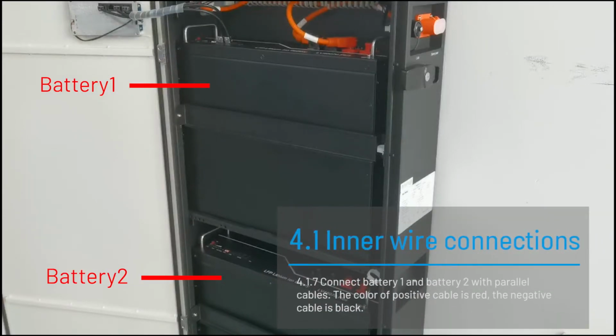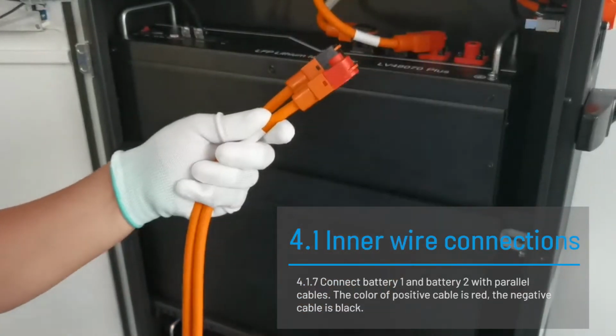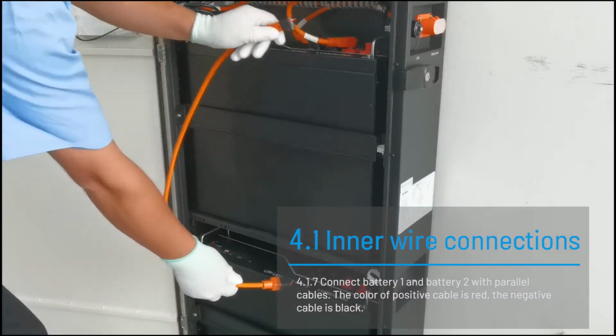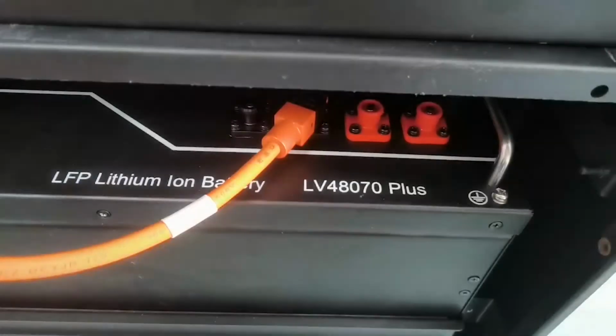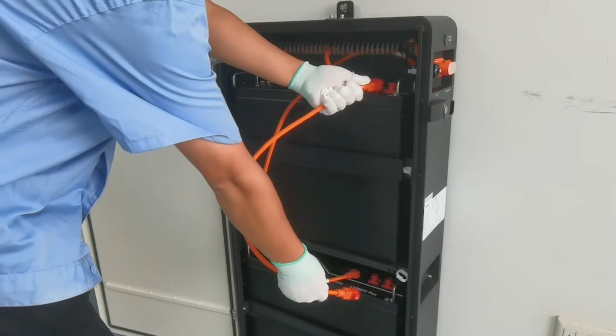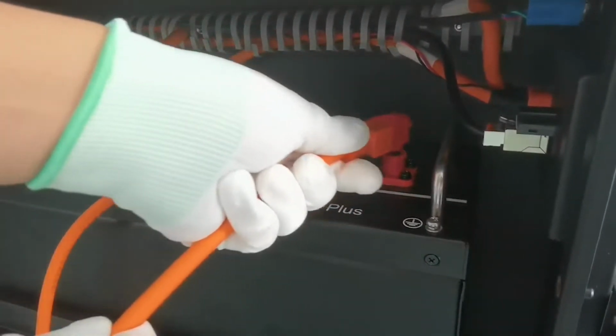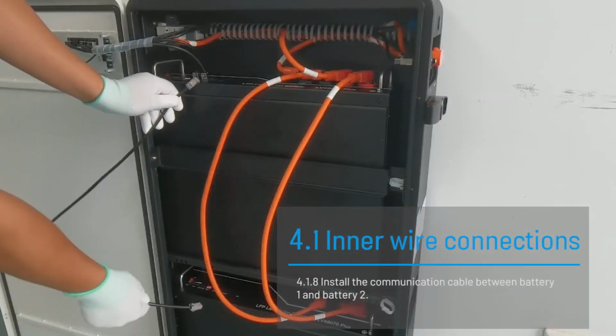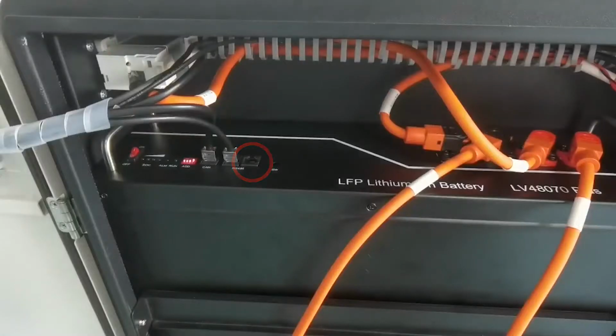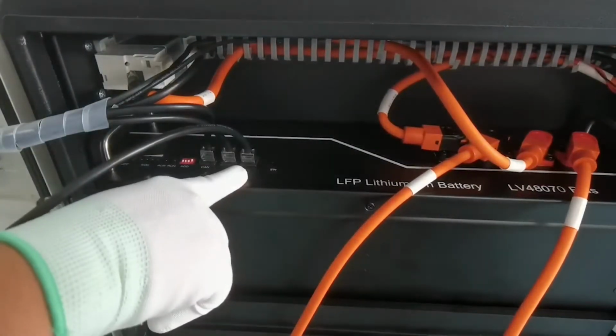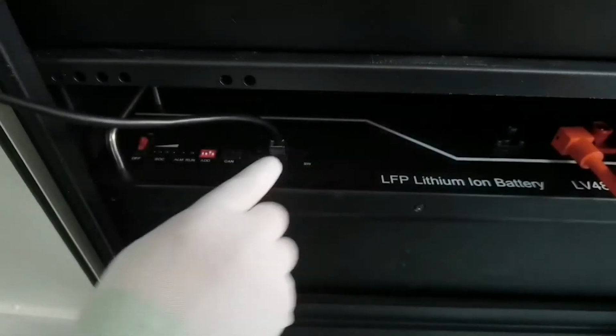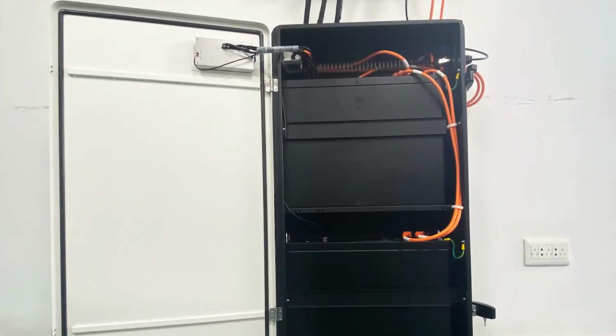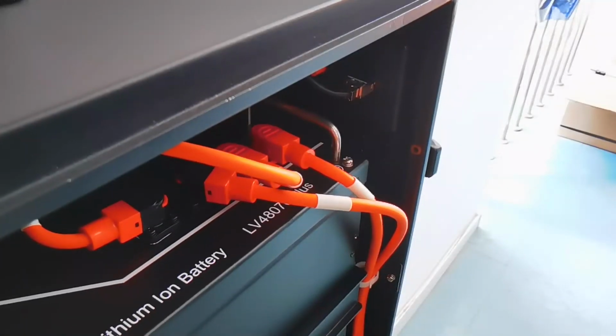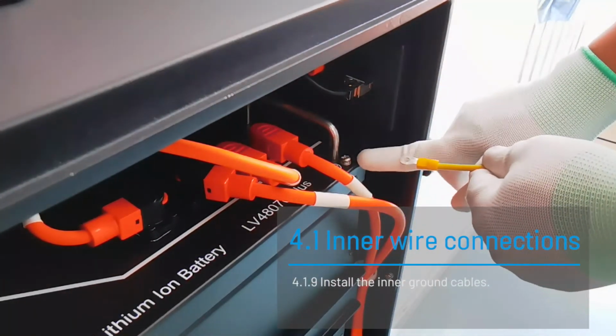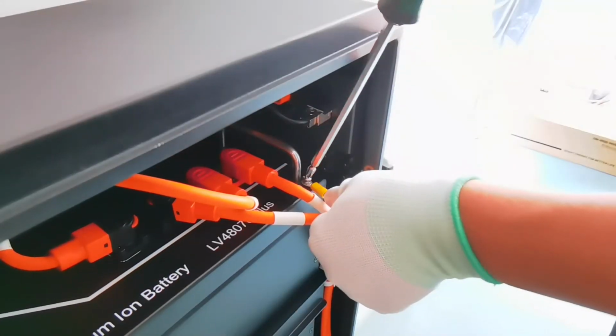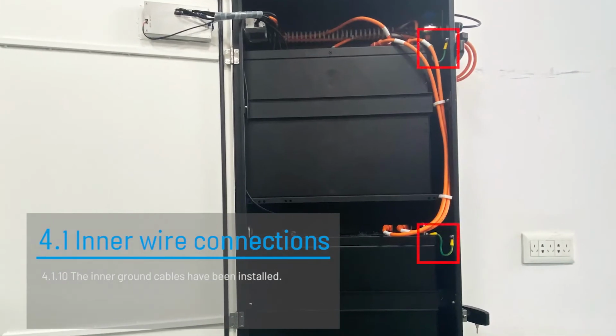Connect battery 1 and battery 2 with parallel cables. The positive cable is red, and the negative cable is black. Install the communication cable between battery 1 and battery 2. Install the inner ground cables. The inner ground cables have been installed.